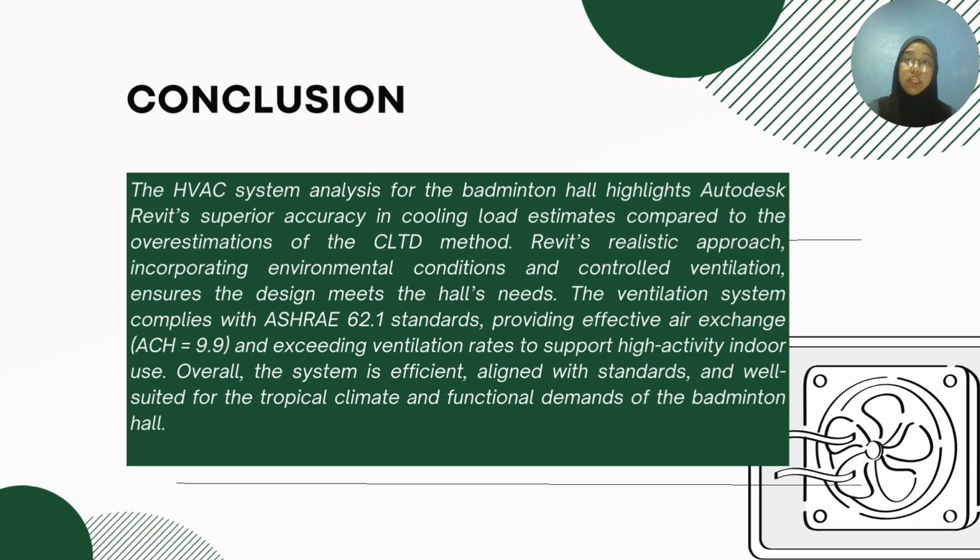For the conclusion, our analysis of the HVAC system design for the badminton hall highlighted significant findings. The comparison of cooling load estimation methods revealed that Autodesk Revit provides a more precise and realistic approach compared to the conservative overestimation of the CLTD method.